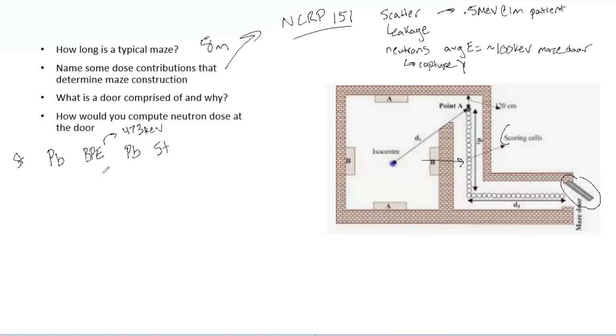And let's talk a little bit about the size of these different pieces. So the steel, typically, we're talking about 0.25 inches, something small. Then we're going to talk about about 3 inches of lead for the first layer. Then about 11 inches of BPE, another 3 inches of lead. Now, this could be less. Typically, obviously, you want to be way more conservative when it comes to these doors and shielding in general.